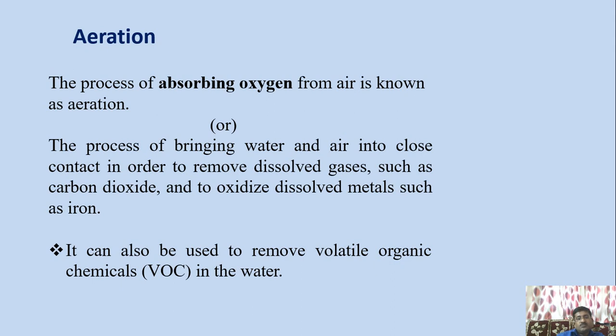The process of absorbing oxygen from air is known as aeration. Alternatively, it can be defined as the process of bringing water and air into close contact in order to remove dissolved gases such as carbon dioxide, to oxidize dissolved metals such as iron, and also to remove volatile organic chemicals, abbreviated as VOC, from the water.